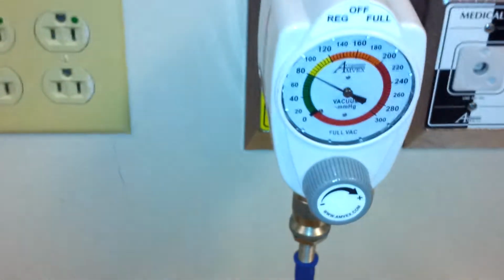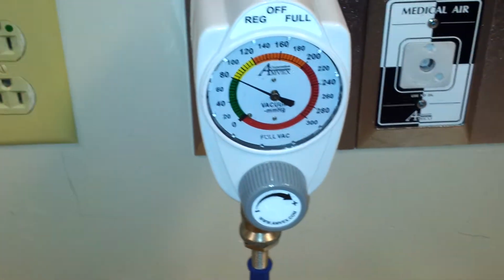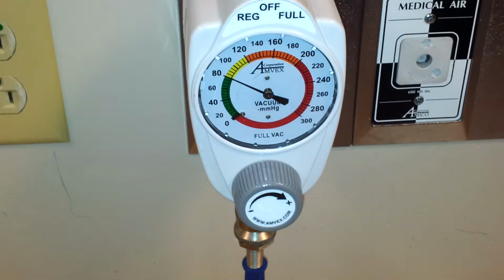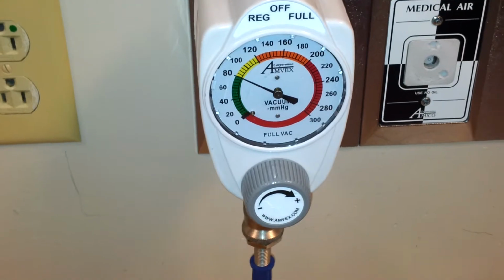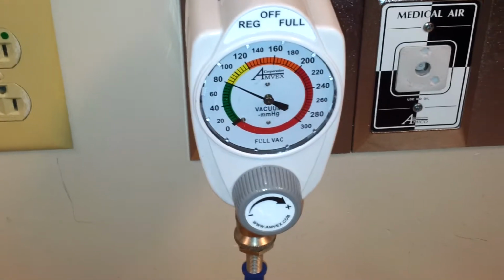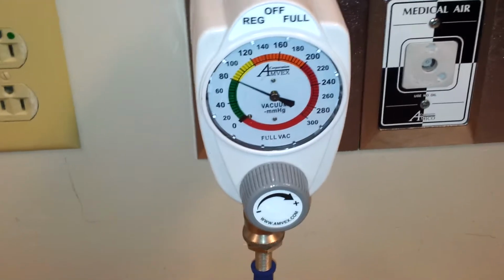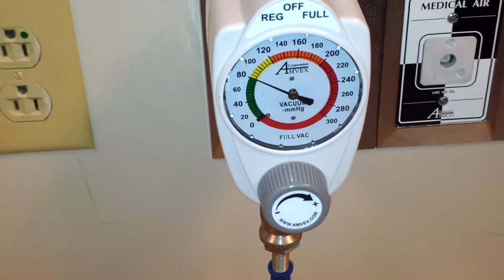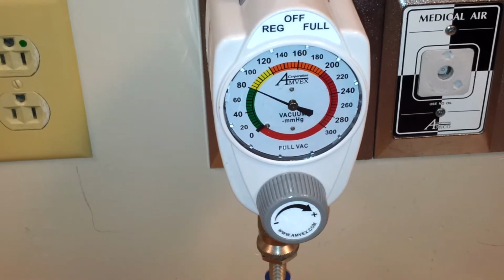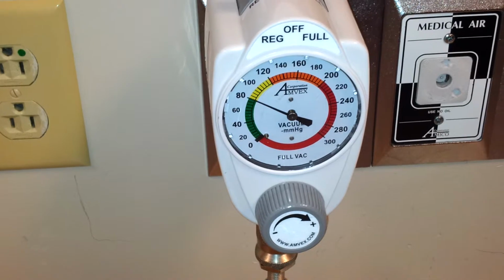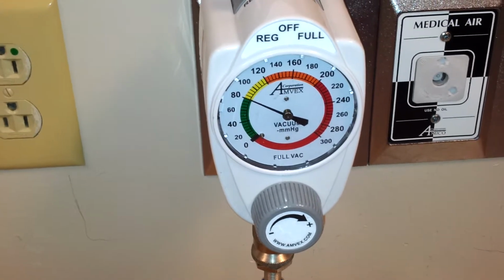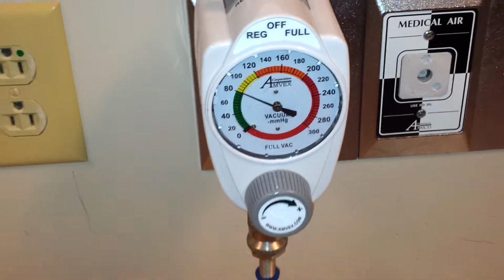The suction levels for the neonatal population for open suction should be set at -50 to -80 millimeters of mercury, which it is set at now. For closed suction, we want to increase the suction pressure by 10 millimeters of mercury. So if we had it set on -80 for open suction, we would change it to -90 for closed suction.